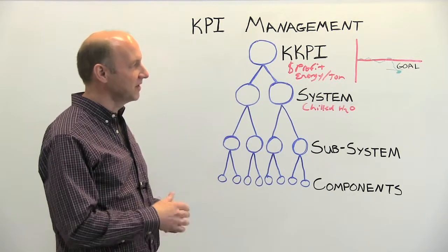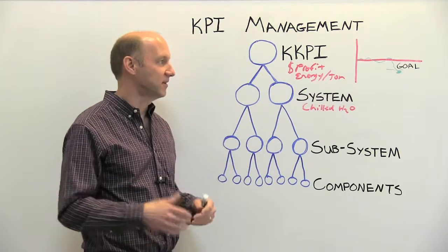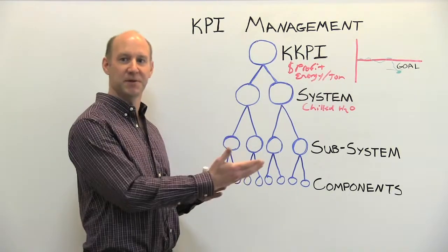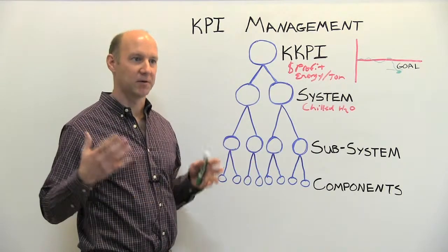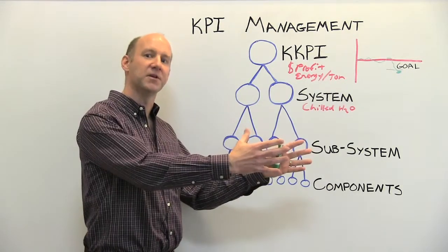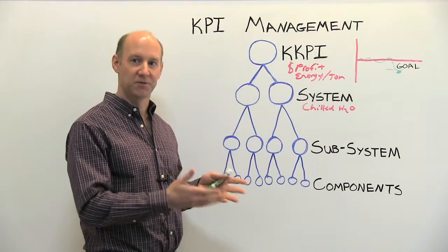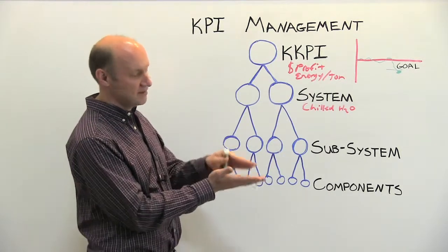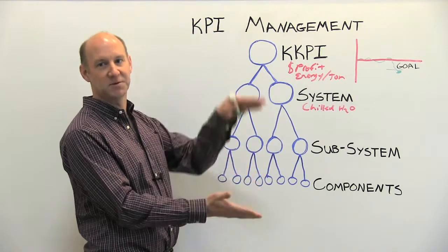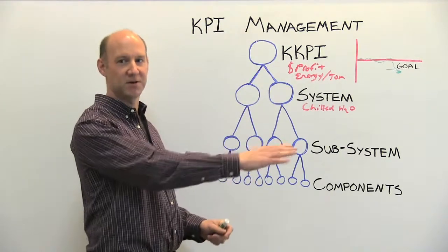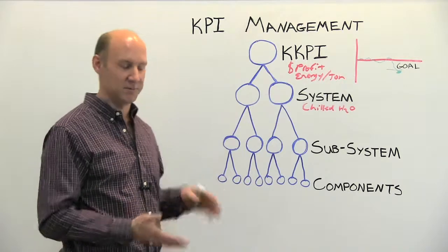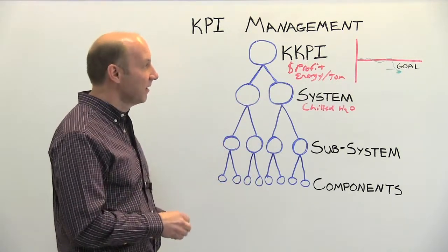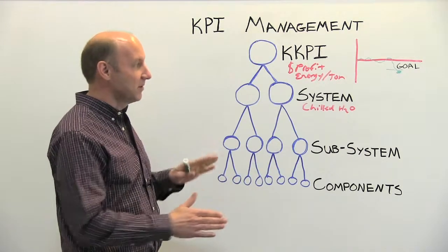And then you can also look at it in terms of theoretical max. You know, what is the maximum performance I can get out of this, or the minimum energy use per ton of metal that I put through the oven. There's a calculable theoretical minimum energy use per ton. If I have to elevate that piece of metal from X temperature to Y temperature as it goes through this process, that would be the theoretical minimum, is what does it take to do that versus what am I actually using to do that. So all of those comparables are good.